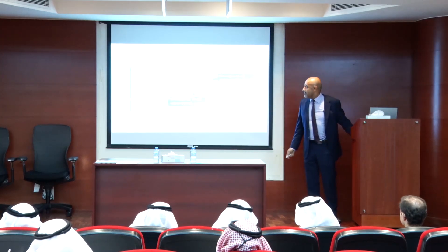Risk aversion — they want to avoid risk. The pump operating range defined by the pump manufacturer is somewhere here. Working outside this range will create cavitation for the pumps, and vibration near the end of the curve. So there is an operating range which differs from pump to pump — I should take it from the manufacturer. When I make my pump station fully automated and optimized, it should work only within that operating range.